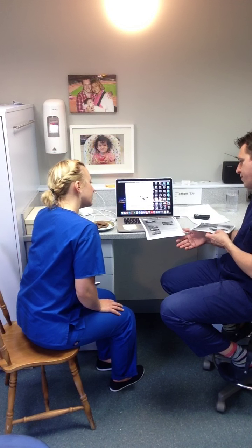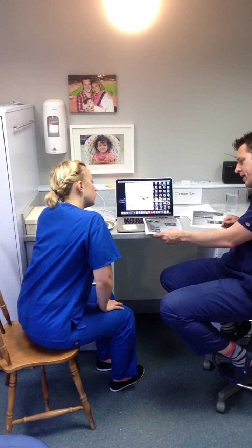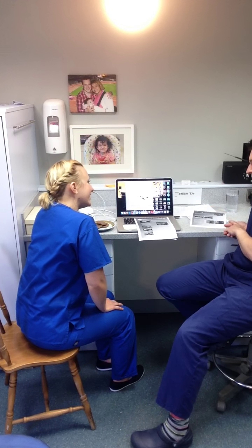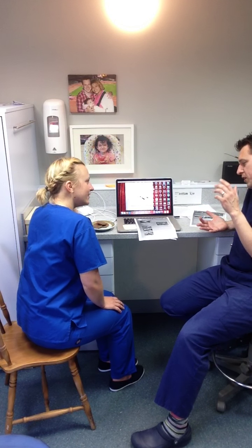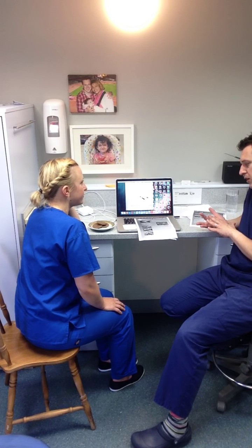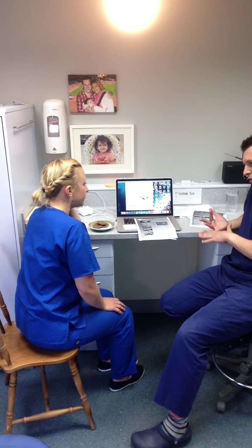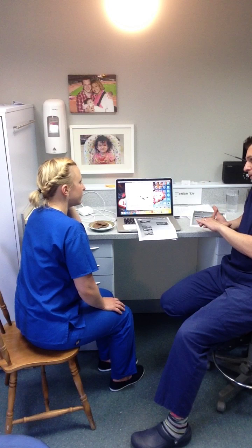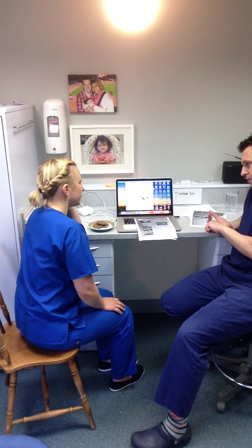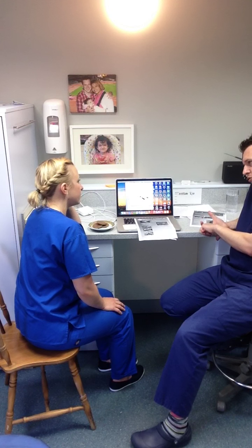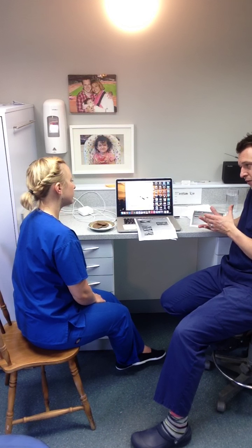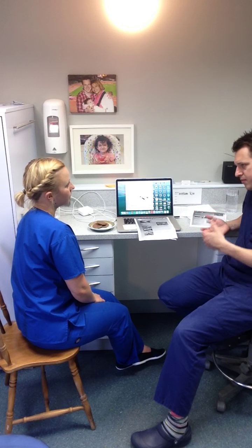Yes. Where we fall short is where? Manual cleaning. Because it's hard to validate manual cleaning. Excellent, good stuff. So we can't validate the manual cleaning. We can't say for sure that we're persistently doing manual cleaning effectively and efficiently every time. The only way we're going to be able to validate it properly is with a washer disinfector. So we fall short on that, and at the minute we're looking to do the ultrasonic bath cleaning as well. Whether we incorporate that as part of the manual cleaning after we've manually cleaned, that's probably something we'll look at doing.